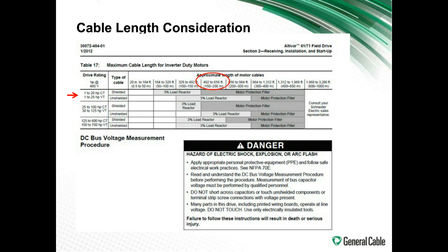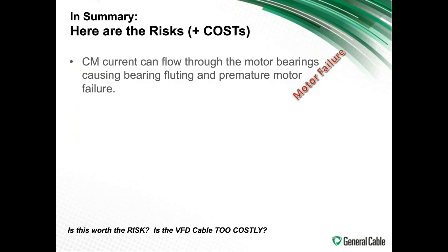So if you even look at 20 feet or 100 feet, it says for a shielded system, you don't need to consider anything. But if anything more, then you're going to need either a 3% load reactor. You're going to need something to account for it. That is good, and that will help with the reflected wave phenomenon. What it does not help, however, with is the common mode current, that sneaky, leaky current that is havoc and cannot be taken care of.